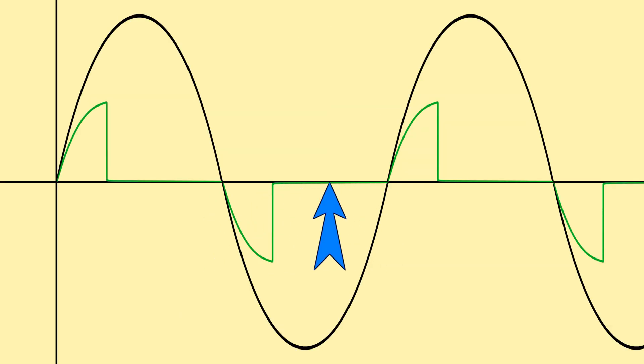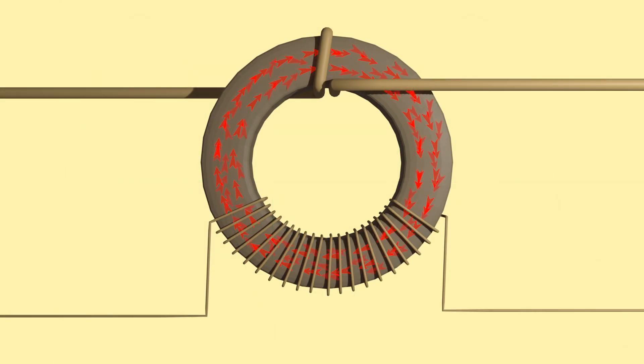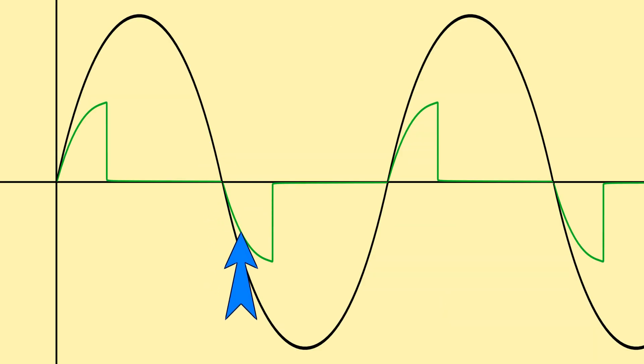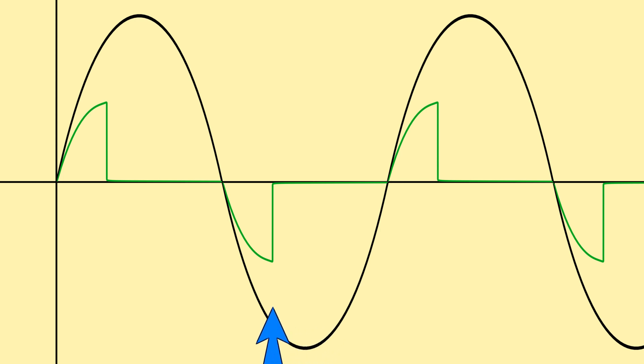During the next half cycle of the primary current, the magnetic force reverses. This reversed magnetic force helps bring the CT core out of saturation — it acts in the opposite direction, providing the necessary external magnetic field to randomize the previously aligned dipoles. As a result, the dipoles begin to reorient, allowing the core to once again respond to changes in the primary current and resume normal transformation. However, after reaching the saturation level again during the next half cycle, the core becomes saturated once more, and the secondary current will again collapse in the same rhythm as it did in the previous half cycle.